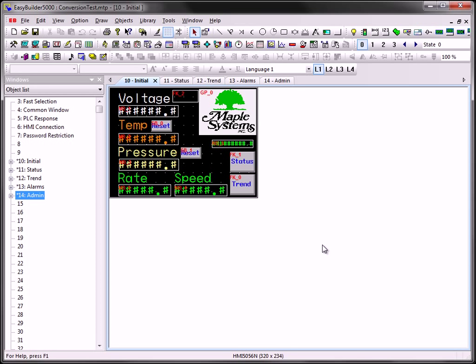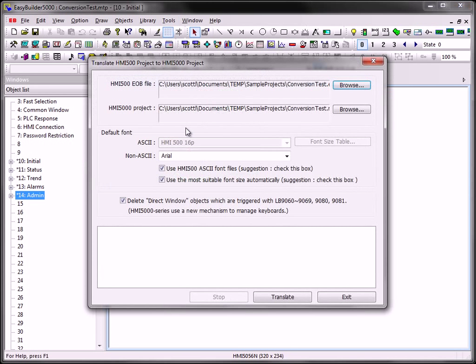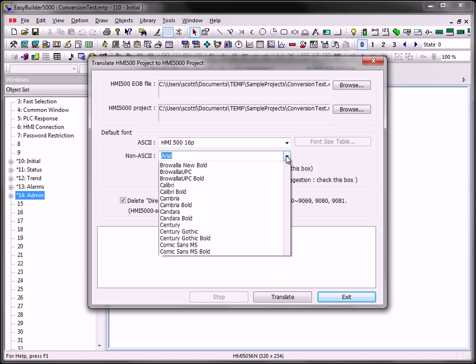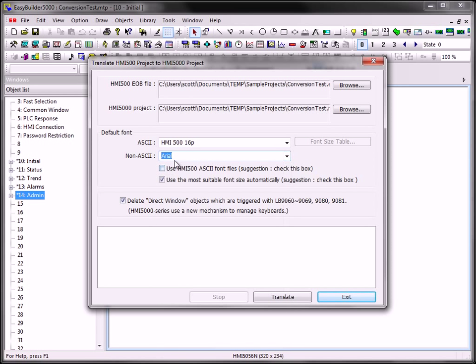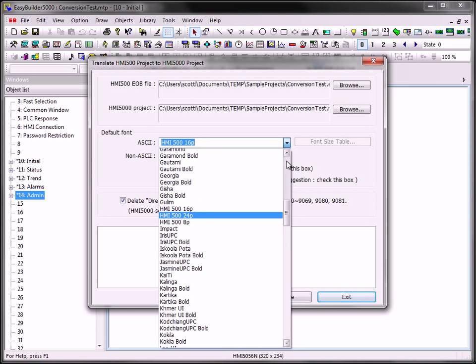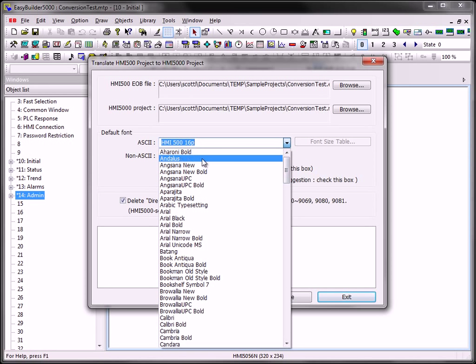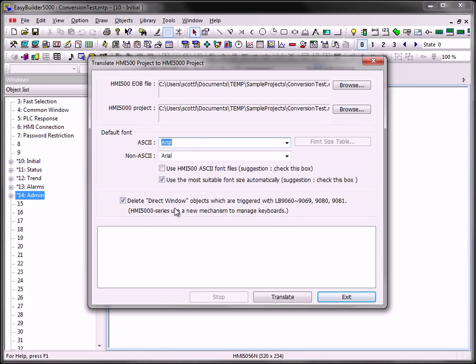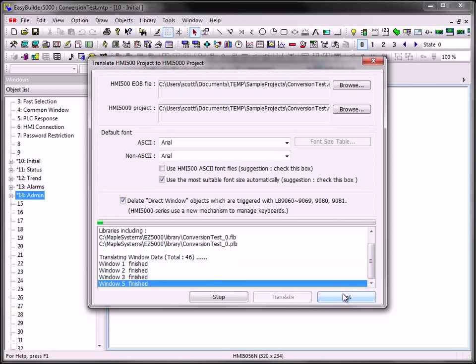You may want to modify the fonts in your project after converting from 500 to take advantage of the TrueType fonts available in EasyBuilder 5000. To modify the fonts, rerun the translation utility, uncheck the Use HMI 500 ASCII font files, select the appropriate font file from the dropdown list, and select Translate.